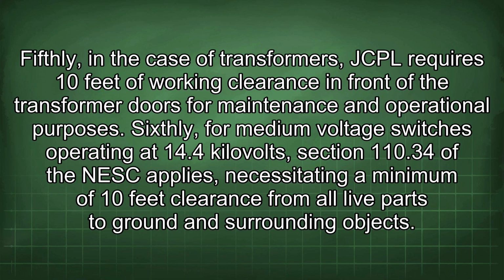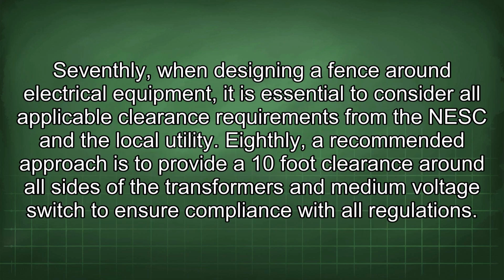Fifthly, in the case of transformers, JCPL requires 10 feet of working clearance in front of the transformer doors for maintenance and operational purposes. Sixthly, for medium voltage switches operating at 14.4 kV, Section 110.34 of the NESC applies, necessitating a minimum of 10 feet clearance from all live parts to ground and surrounding objects. Seventhly, when designing a fence around electrical equipment, it is essential to consider all applicable clearance requirements from the NESC and the local utility. Eighthly, a recommended approach is to provide a 10-foot clearance around all sides of the transformers and medium voltage switch to ensure compliance with all regulations.